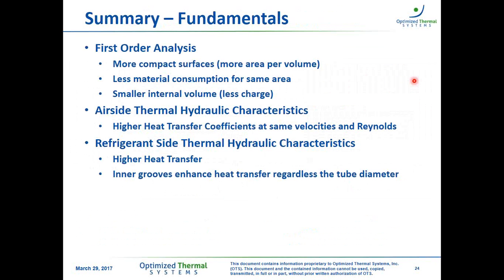Okay, so this was the fundamental section. So let's just summarize the advantages that we learned from the fundamentals. From the first order analysis perspective, the smaller tube diameters give us more compact surfaces, or more area per volume, give us less material consumption for the same area, and a smaller internal volume, which can be translated into less charge. For both the air side and the refrigerant side, the heat transfer coefficients increase significantly as we reduce the tube diameter at the same velocities and Reynolds numbers.